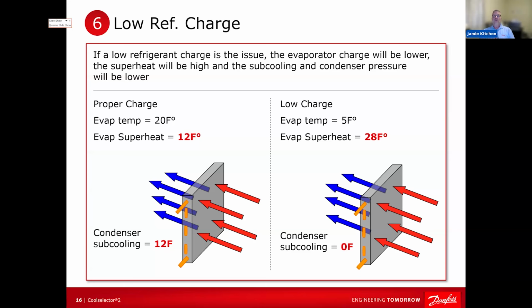If you take those same measurements and your evaporator temperature goes down and your superheat goes in the opposite direction, goes up, that means you don't have enough refrigerant in your evaporator. It doesn't tell you you're low on charge. It just tells you you don't have enough refrigerant in your evaporator. But you know what does tell you if you have enough charge or not? Is the subcooling on your condenser.